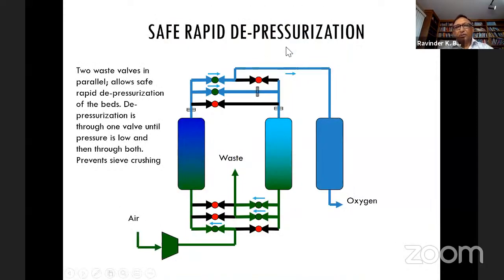And one thing which I mentioned, to prevent crushing of the sieve, we cannot be depressurizing it very, very fast. But in PSA process, we do need to depressurize it fast. We don't have too much longer cycle times. You need a lot of adsorbent. So what we do is, for the waste valves where we depressurize, we put 2 valves and we open them sequentially. We open a small valve first and let the bed pressure come down to a certain level, and then we open the second valve to depressurize the rest. So that is the way we do the depressurization.